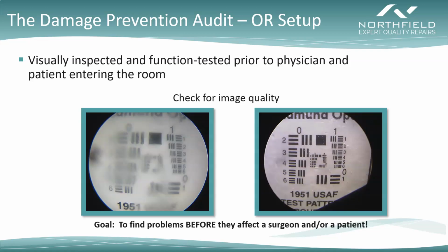And it's really easy to just very quickly check for image quality to make sure that it's bright and clear. And remember that the goal is always to find the problems before they affect the surgeon and a patient. One thing we've talked about frequently is how even in a best case scenario, when there's a surgical site failure of a device and all they have to do is stop and go get a new scope or a new device, that still adds time to the surgery, that still adds stress to the room. And we want to prevent that as much as possible.